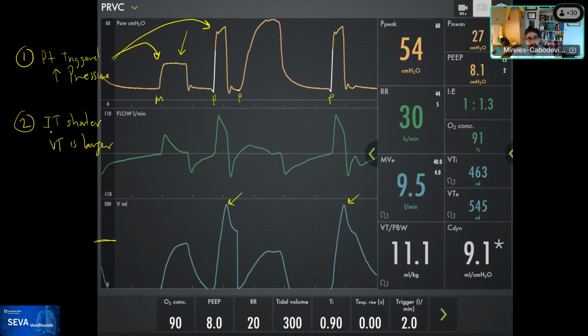The second observation is that the I time is shorter when the tidal volume is larger, has to do with a safety feature that occurs on this ventilator, in which when the tidal volume has reached, I think it's 1.5 times the tidal volume that you set, so meaning 450, it will cycle off. So the patient took a breath in, it continued to do effort, and it triggered the next breath, but it reached 450, and so boom, it cycles off the breath. And so that's why you get a shorter I time. This is not the patient cycle, it's a machine cycle, just to try to limit the tidal volume that the patient gets. And you can see the example here. Here it caused a double trigger. Here it caused a double trigger.